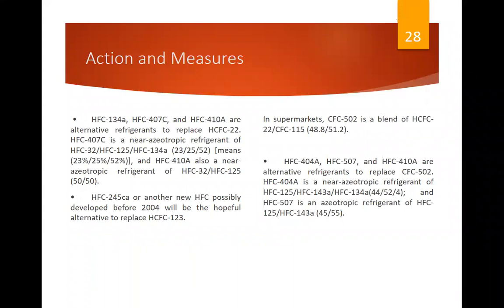HFC 245CA or another new HFC possibly developed before 2004 will be the hopeful alternative to replace HCFC 123. In supermarkets, CFC 502 is a blend of HCFC 22 and CFC 115. It's made of 48.8 and 51.2%. Then HFC 404A, HFC 507, and HFC 410A are alternative refrigerant to replace CFC 502. HFC 404A is a near azeotropic refrigerant of HFC 125 and HFC 143A and HFC 134A. That's 44, 52, and 4. And HFC 507 is an azeotropic refrigerant of HFC 125 and HFC 143A. It's 45-55%.